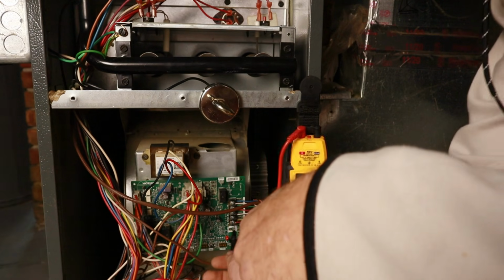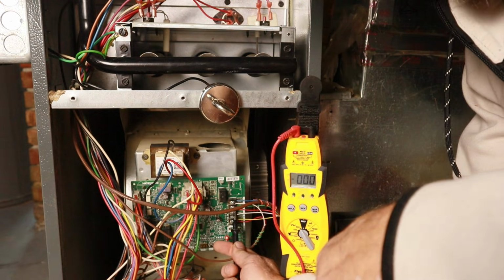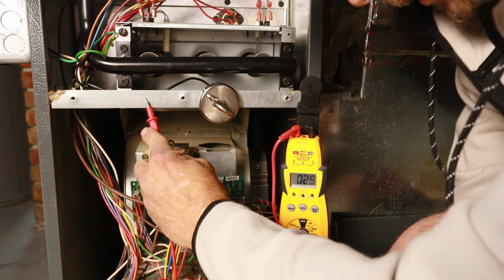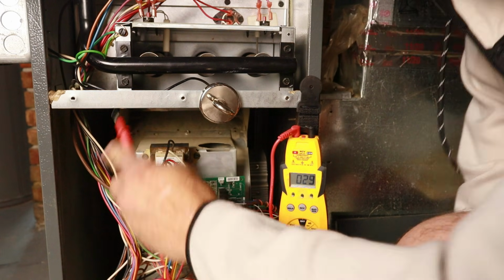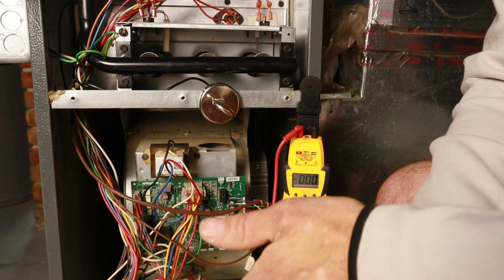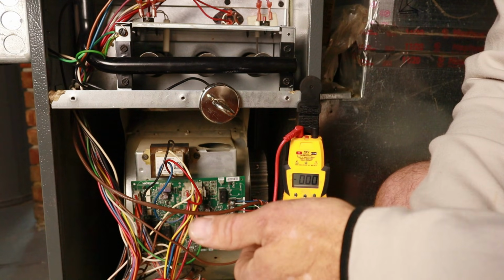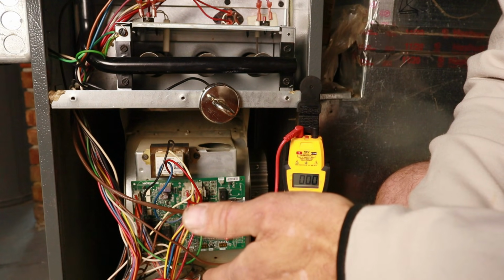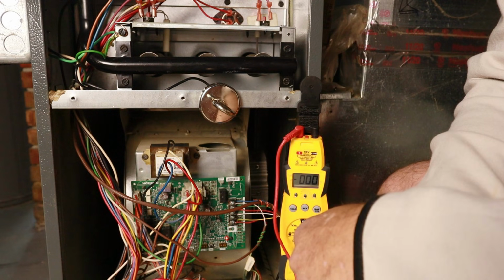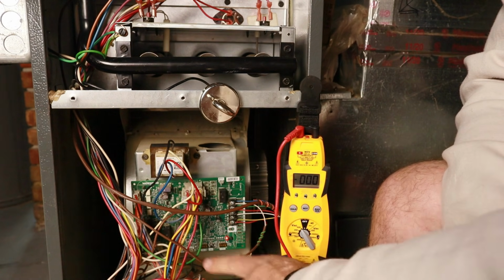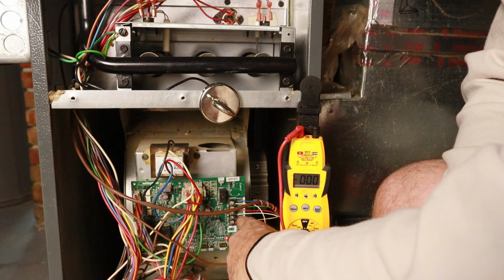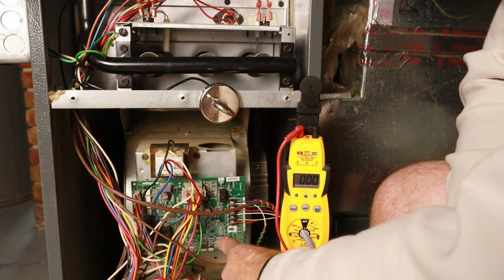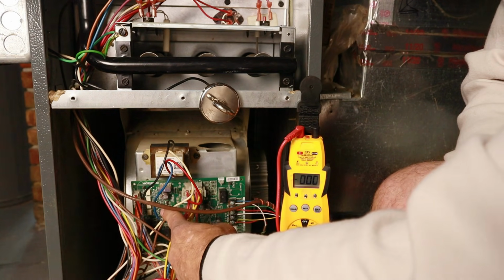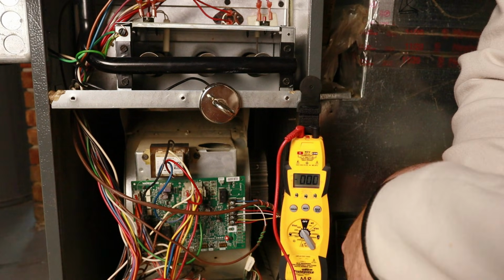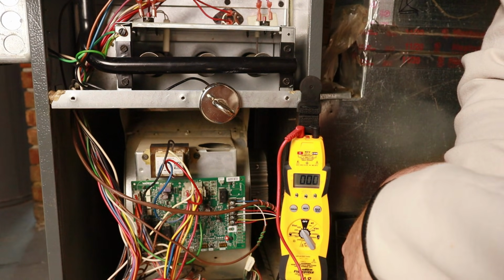I read 0 volts. Put that back on, turn our power back on again, and when I go back to that R terminal, I am once again reading 29 volts. So, like I said, this is not something you always see in schematics. A lot of guys don't teach you this. Sometimes it's just something you've got to figure out on your own sooner or later. But you can rest assured, if you're ever getting this far into a diagnostic procedure and you're not reading 29 volts or whatever the voltage is on that R terminal, and you do have it on your fuse, you want to start checking the safeties in your heating circuit.